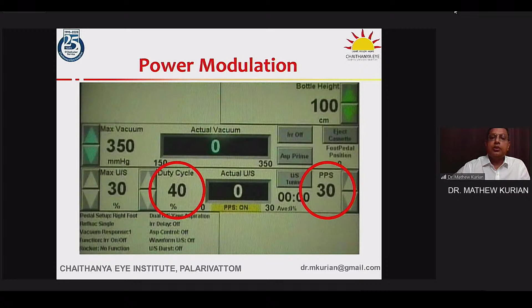It led to 2 concepts. One is burst, where as you enter foot position 3, you go to the preset maximum and the duty cycle is in linear control, whereas the power is fixed, which means that as you go further down in foot position 3, the interval between the on-off cycles becomes lesser and lesser till eventually you're delivering continuous power.